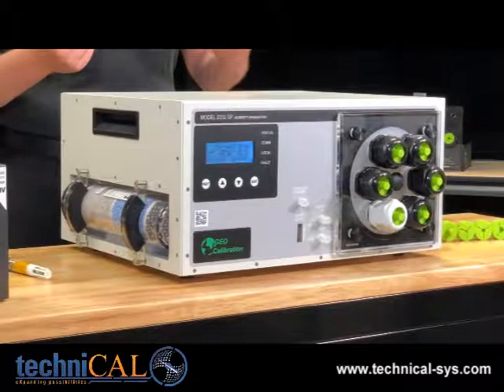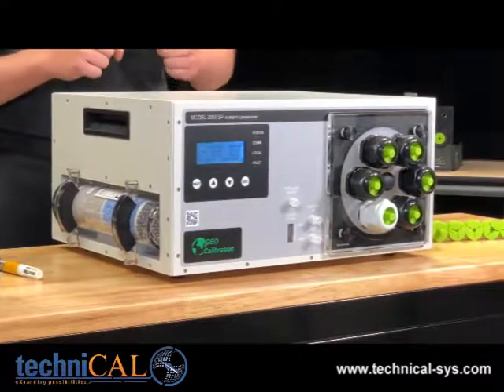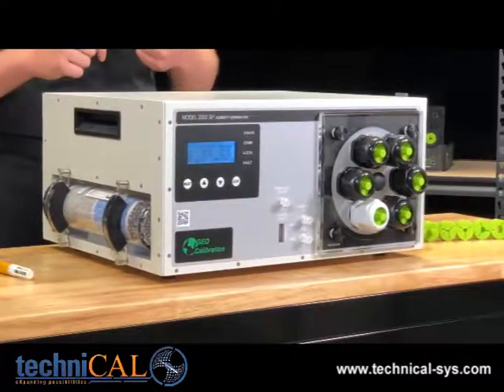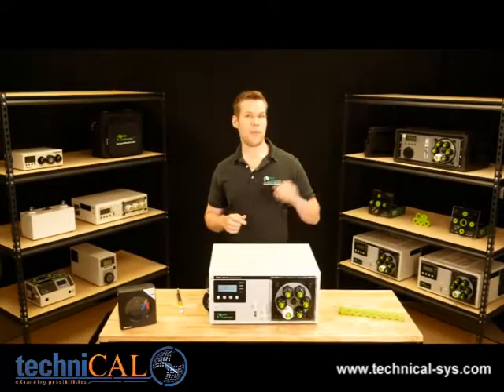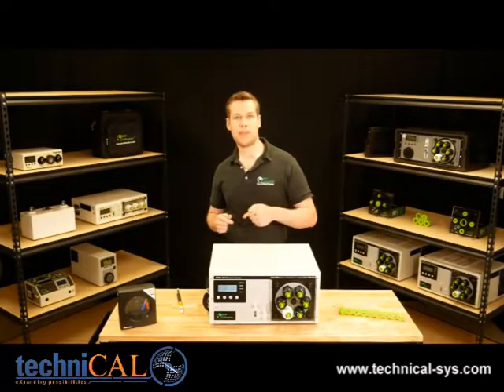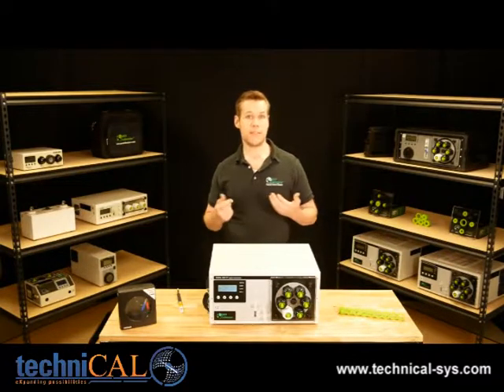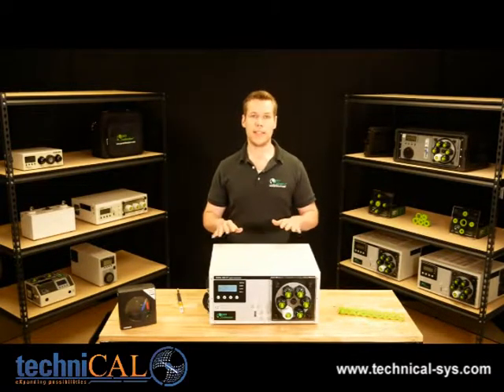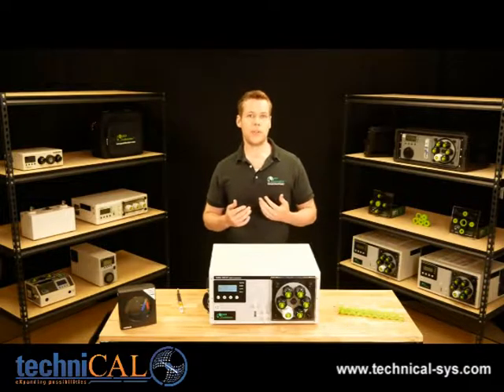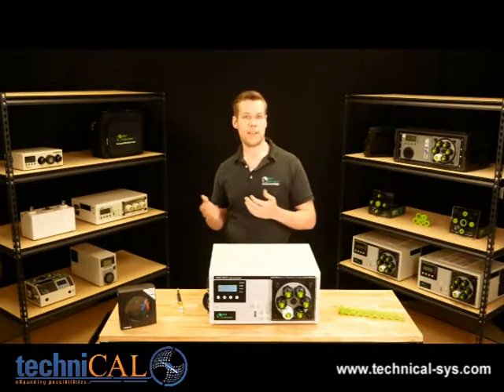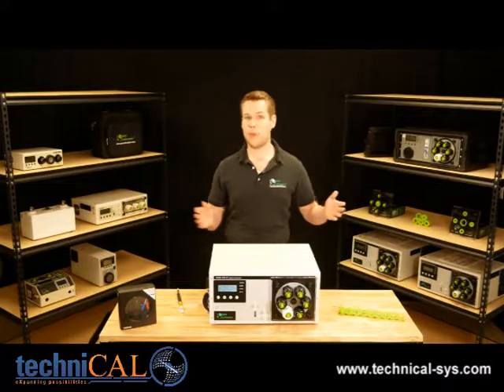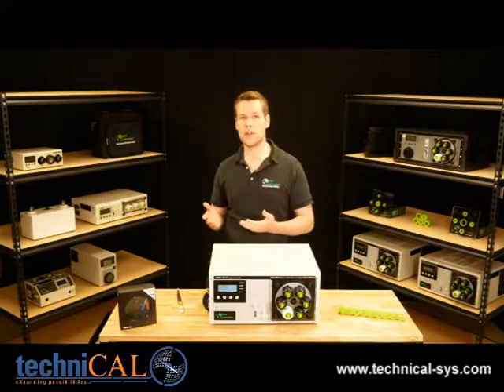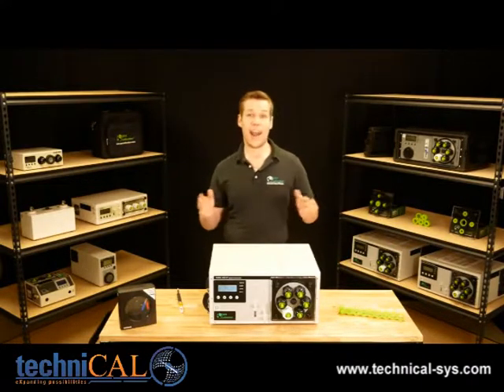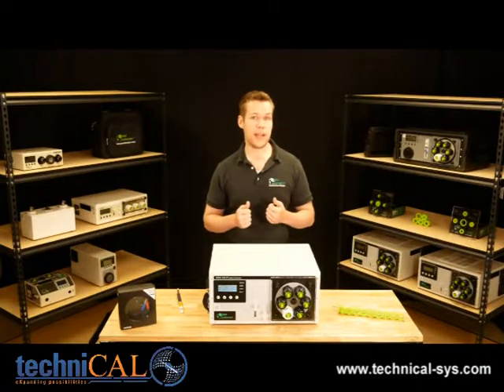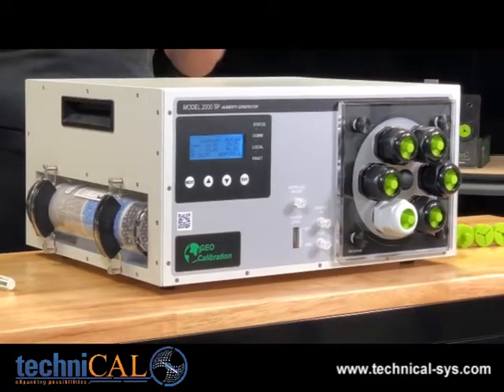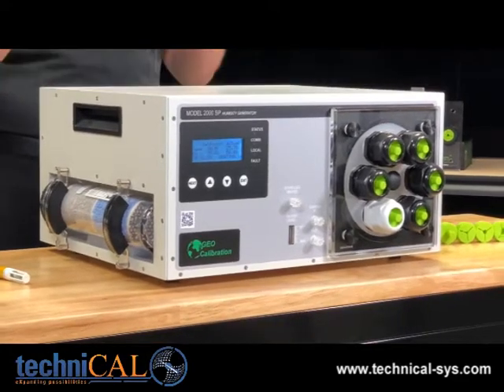At 23 degrees Celsius, this unit can start at 5% RH and settle at 95% RH in less than 3 minutes. It can perform a 5-point temperature cal when cooling from 25 to 15 degrees Celsius in less than 40 minutes. This chamber is so fast and so easy that your only concern is going to be the settling time of the humidity device that you're calibrating. So right now, if you've paid $50,000 for a 2-pressure generator, and you're waiting 8 to 10 hours to complete a 3-point temperature cal, at less than $20,000, you should really consider the GEO 2000 SP for your lab.